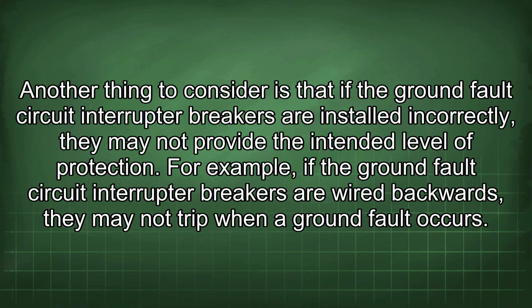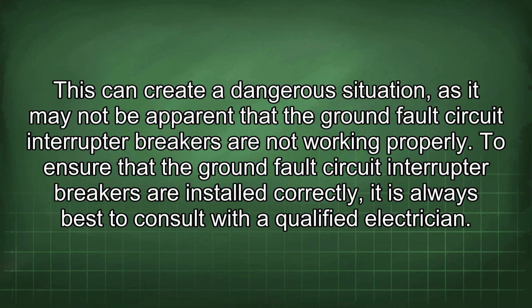Another thing to consider is that if the ground fault circuit interrupter breakers are installed incorrectly, they may not provide the intended level of protection. For example, if the ground fault circuit interrupter breakers are wired backwards, they may not trip when a ground fault occurs. This can create a dangerous situation, as it may not be apparent that the ground fault circuit interrupter breakers are not working properly.